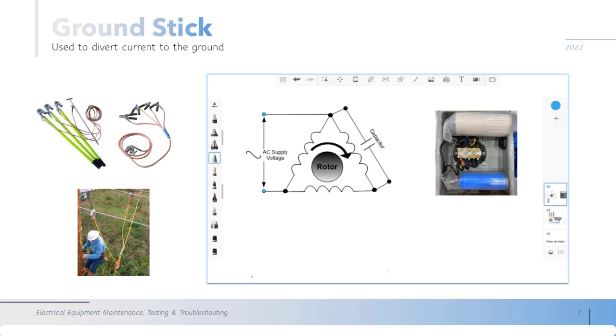So when you want to work in these terminals of the motor and you open the power supply in these terminals, you get 0 volts. You cannot start working here directly because this capacitor is still charged. The capacitor stores energy. If you touch this terminal, this one or this one, you will get electrocuted because this capacitor is charged and the voltage is approximately the voltage applied.